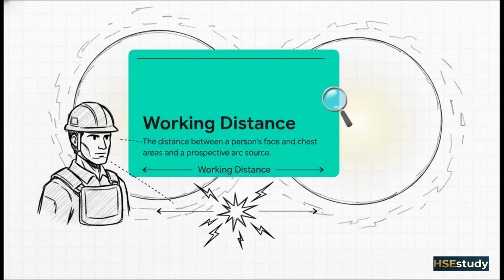NFPA 70E gives us the official definition, but it all comes down to the inverse square law. It's just physics. Simply put, the energy of that blast dissipates exponentially the further you get from it. Doubling your distance doesn't cut the energy in half. It cuts it down to a quarter. In an arc flash event, distance is your absolute best friend.